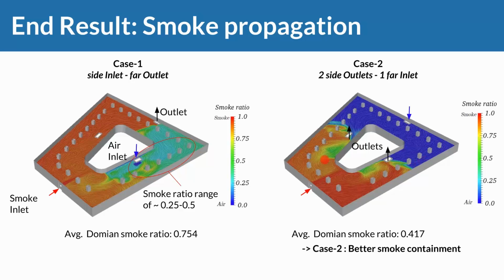On the right, with the second outlet on, we can see that basically we have this air curtain movement happening, and just half of the parking lot is filled with smoke, which again gives us a better performance of our building, of our parking garage, with respect to smoke propagation.